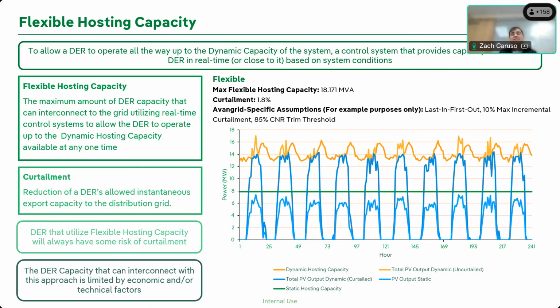So obviously there is an economic level that we can get to, where the amount of curtailment, the amount of energy that I'm getting out of the incremental megawatt, is equal to the cost to install, build and maintain that additional megawatt. And there's also, which I will probably get into at the end, the idea of additional technical limits. As a utility, I also don't want to have 50 megawatts of generation on a 20 MVA bank, for fail-safe and N-1 reasons, right? That makes things more operationally complex, especially when I'm relying on a single control system to back me up there. So there are operational considerations that also have to be worked in.